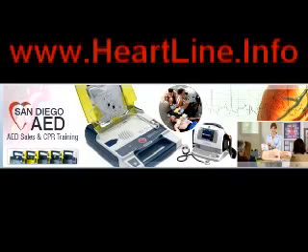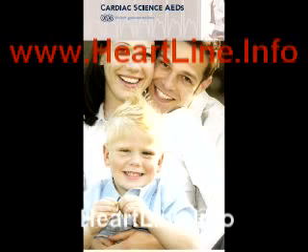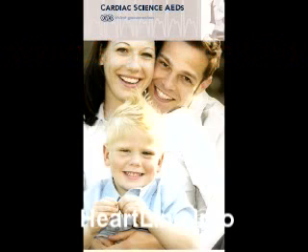The AED does not require any maintenance checks. The device is going to do it itself, even though some states do require a monthly inspection, which is great. However, with our checks, basically the only thing you have to do is just make sure that indicator is green, and then you can always look at the expiration date on the pads without even touching the AED through our clear see-through lid.